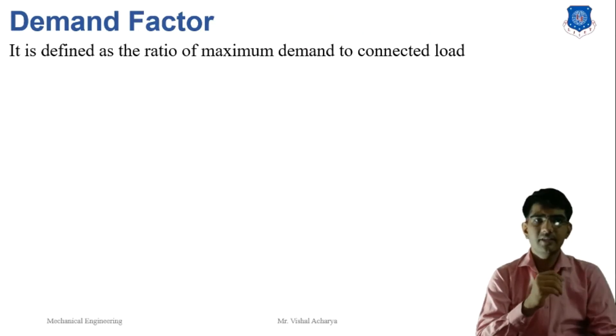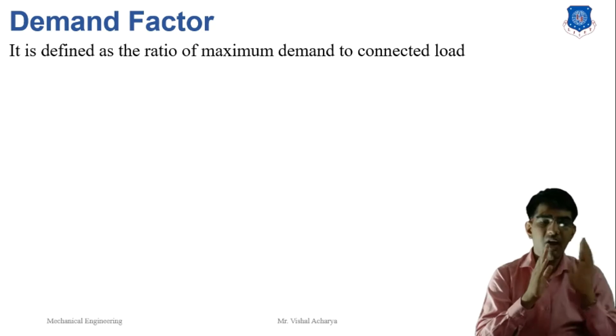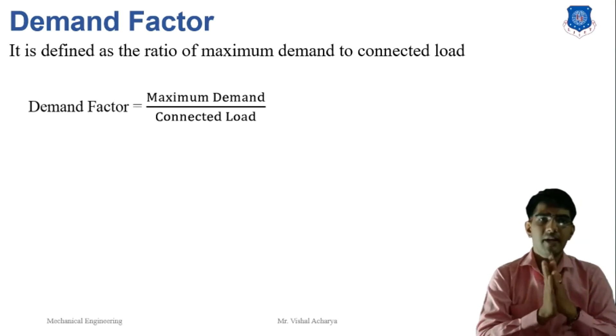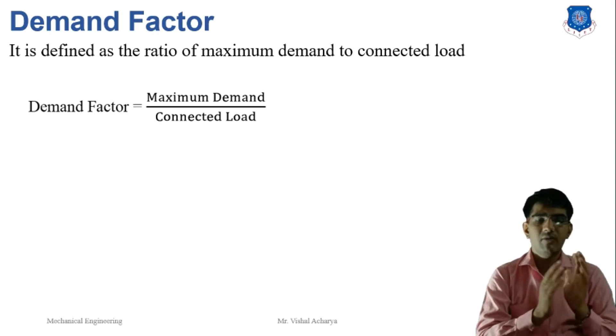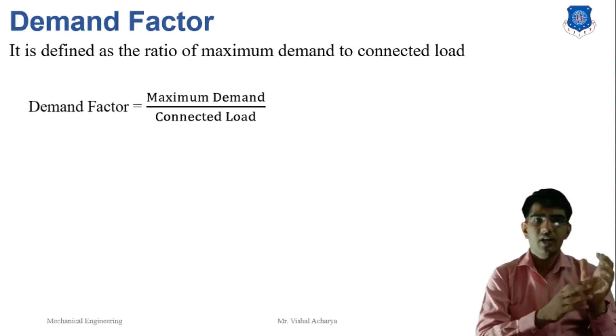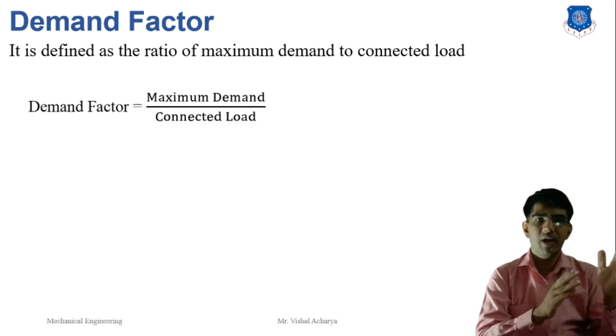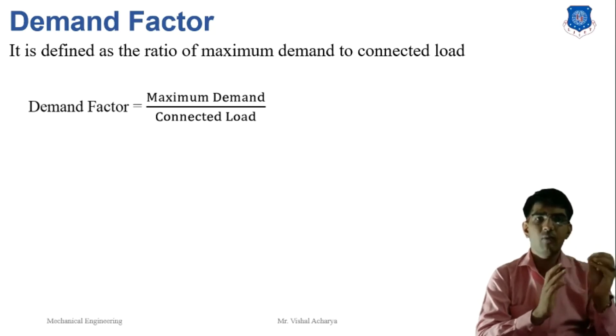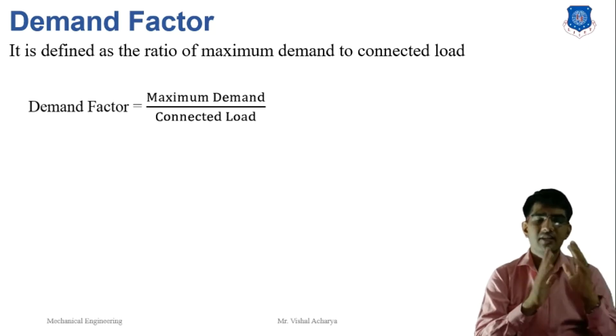Next is the demand factor. Demand factor is the ratio of the maximum demand to the connected load. For example, if maximum demand is 500 and connected load is 1745, then the demand factor is 500 divided by 1745. Demand factor is always less than 1 because maximum demand is always less than the connected load.